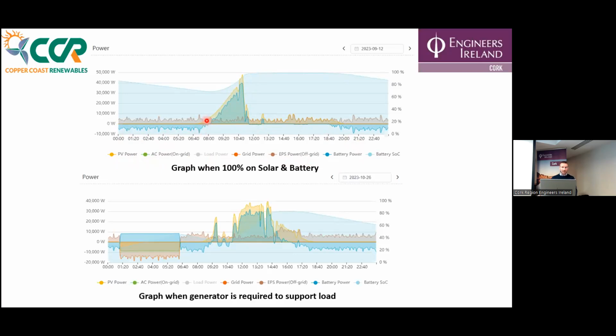But the solar, you can see this blue line, this kind of blue underline with these peaks, that matches the load here. That's when we were running on battery. The solar then kicked in, took over the load, and also charged up the battery. That's the height difference between this dark blue and yellow. But then over here, the batteries were fully discharged or fully charged to 100%, which you can see by the state of charge line.